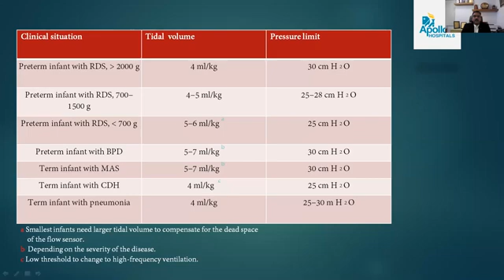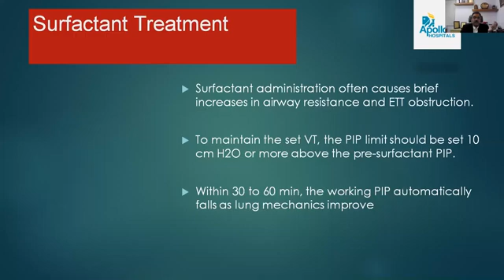Surfactant treatment. Surfactant administration often causes a brief increase in airway resistance and endotracheal tube obstruction. To maintain the set tidal volume, the PIP limit should be set 10 cm or more above the pre-surfactant PIP. Within 30 to 60 minutes, the working PIP automatically falls as the lung mechanics improve. Suppose you are doing volume ventilation and giving surfactant: because the ventilator is sensing the tidal volume, the pressure will automatically come down after surfactant as the compliance improves.